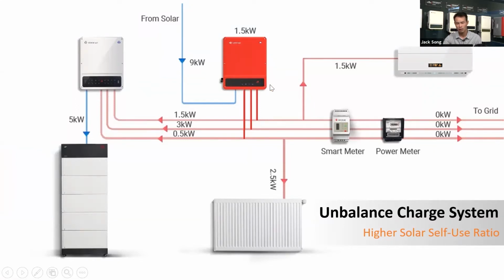It is used with a three-phase on-grid inverter here, and from the solar power we have 9 kilowatts, and the power of the loads is not so high, so they cannot use all the power from the solar. The rest of the solar will be used to charge the battery. Its priority is load first and then battery, right? Like here, the total load power is 4 kilowatts, and the power from solar is 9 kilowatts. So there are another 5 kilowatts to charge the battery.